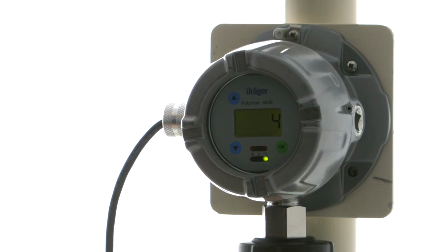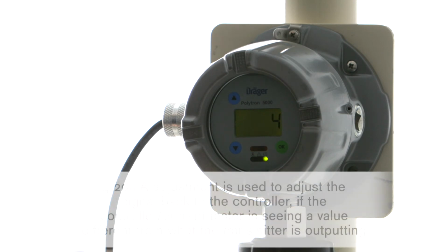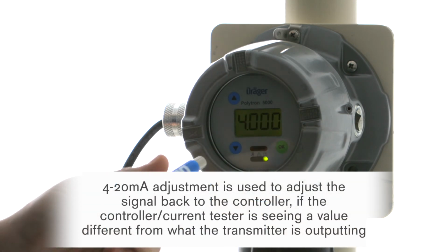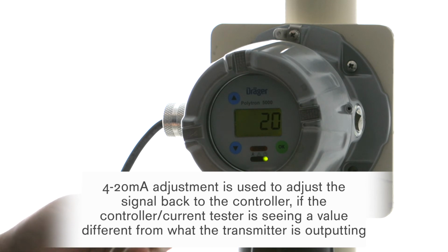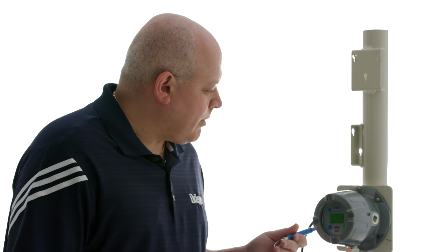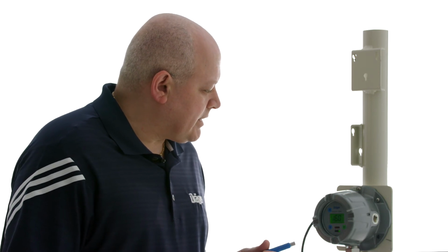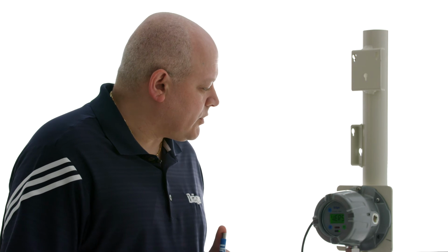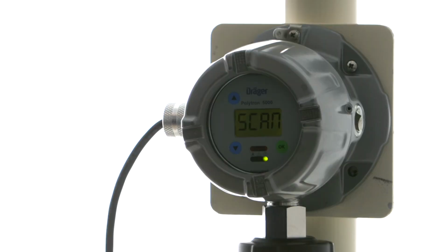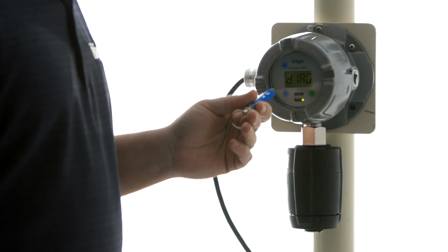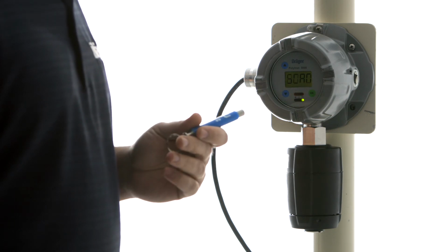We can also adjust the 4 milliamp output, as well as adjust the 20 milliamp output. Once we adjust it, we get back to the main menu, and then the next thing it's going to show us is the version of the software that we have, and the diagnostic scan. The diagnostic scan is typically used by our service group, so most of the time end users do not have to worry about the diagnostic scan unless being asked by our service team. And that's our last menu item.